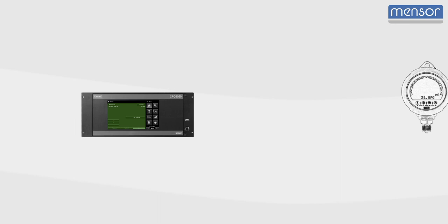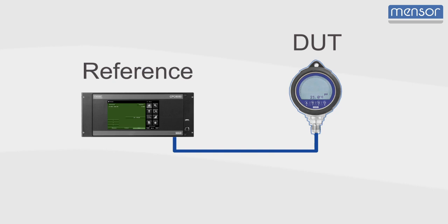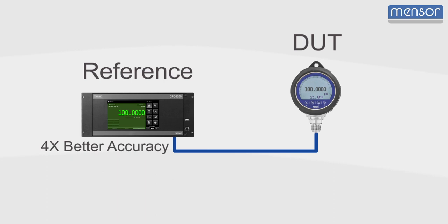In pressure calibration, it is crucial to know the accuracy of both the reference instrument and device under test. The calibrator or reference instrument must be more accurate than the device being tested. It is recommended the accuracy of the calibrator be four times better than the device being tested at every point in the calibration.